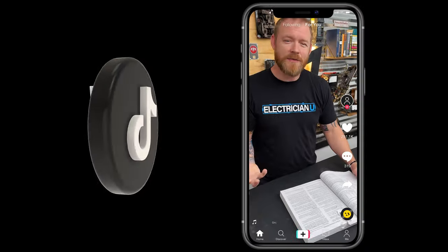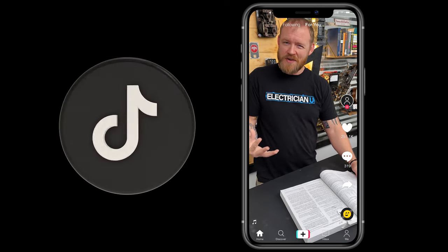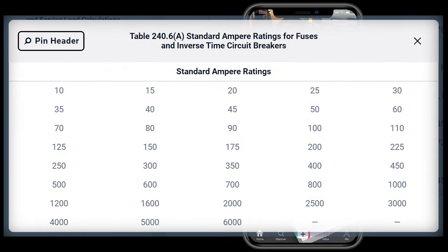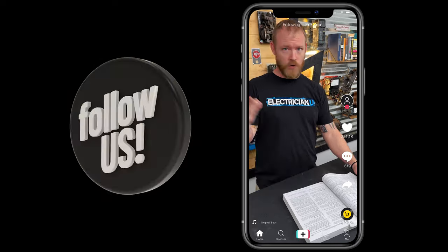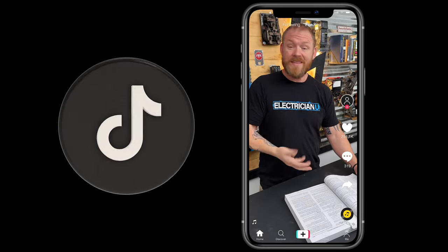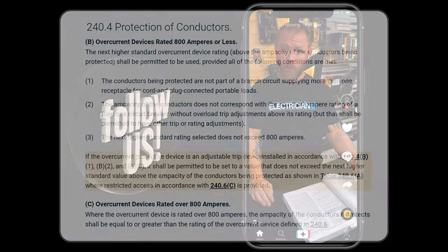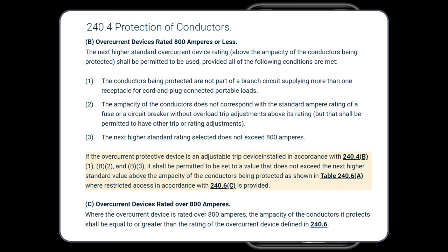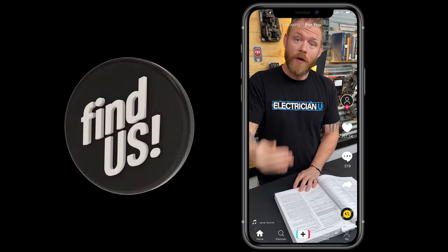If you're at a supply house trying to get breakers, there are standardized breaker sizes in our industry. In the NEC at Table 240.6(A), there's a chart of all standardized circuit breaker sizes. If you're in between sizes, code section 240.4(B) and (C) talk about rounding up to the next breaker size if you're up to 800 amps, but once you exceed 800 amps you cannot round up. There are also conditions in 240.4(B) — items one, two, and three — that must all be met in order to round up.